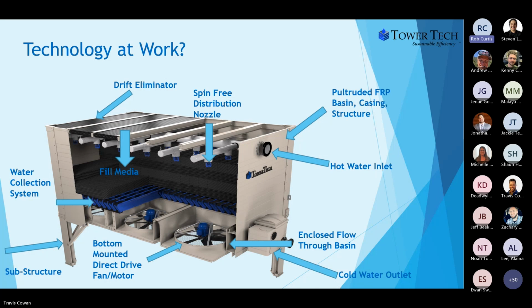The other part of that is now your mechanical equipment is a direct drive piece of equipment which uses multiple fans and motors. So you're using 5, 3, 7.5 horsepower motors with small diameter fans, as compared to a traditional design that has a larger 50, 75, whatever it is, with larger diameter fans, where you usually have to use cranes, scaffolding, something to get that mechanical equipment off the top of the tower. So with TowerTech, you can go in and remove that fan and motor, being on grade level, and it's a 17, 18 pound fan. So it's real easy to remove.